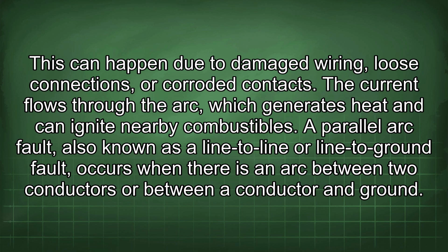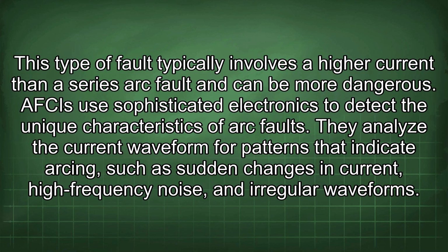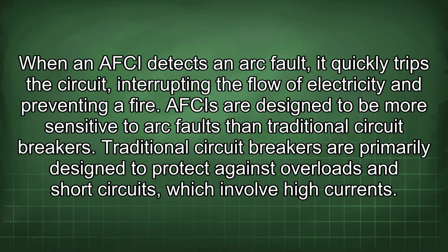A parallel arc fault, also known as a line-to-line or line-to-ground fault, occurs when there is an arc between two conductors or between a conductor and ground. This type of fault typically involves a higher current than a series arc fault and can be more dangerous. AFCIs use sophisticated electronics to detect the unique characteristics of arc faults. They analyze the current waveform for patterns that indicate arcing, such as sudden changes in current, high-frequency noise, and irregular waveforms. When an AFCI detects an arc fault, it quickly trips the circuit, interrupting the flow of electricity and preventing a fire.